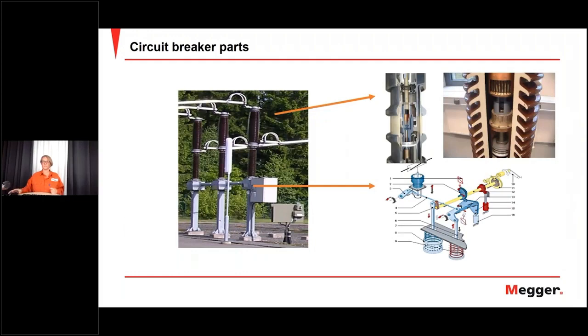We are going to focus a little bit more today on the SF6 circuit breakers. And here we have an SF6 breaker with the different parts. You have a nozzle here, the gray part, and inside is the arcing contact. The nozzle here is to protect the main contact, which is outside the nozzle, because the arcing is performed inside between the two arcing contacts.